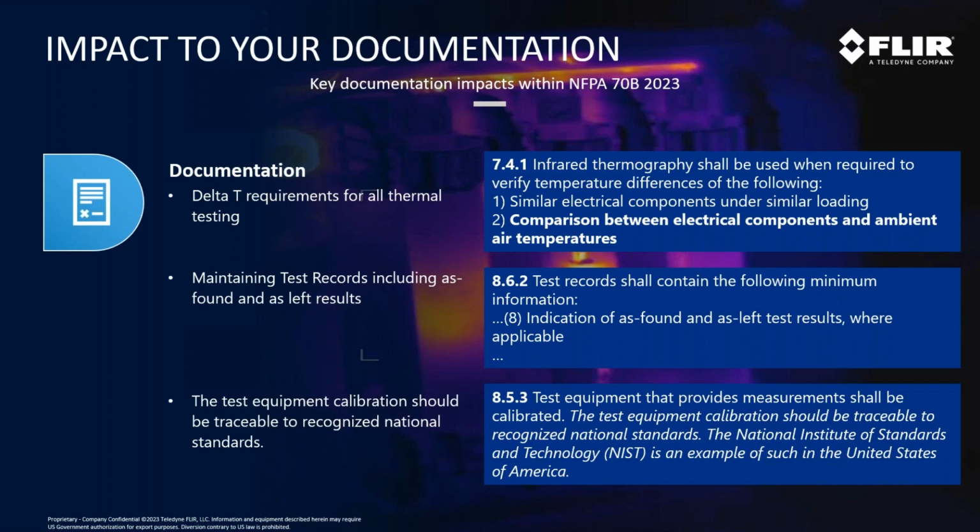And these are situations where some organizations will hire out a company to come in and do their thermal inspections, and then provide the reports back to you, and you go out and you make your repairs. You need to now document the as found condition. So if there was a problem, as well as left where applicable.